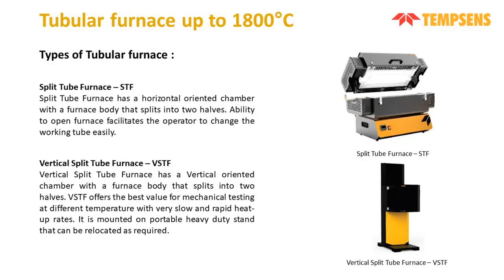Now coming to the types of tubular furnace that we have. We have different types of tube furnace. First, let's talk about the split tube furnace. Basically, the split tube furnace is a horizontally oriented chamber which we can open to a particular angle. We can take out the tube and insert the material, which makes it easy to load the material inside the furnace. Now coming to the vertical split tube furnace, we have a vertical chamber which we can open at a vertical section. These are the same as the split tube furnace, which we see in horizontal; the same we can go for a vertical part.